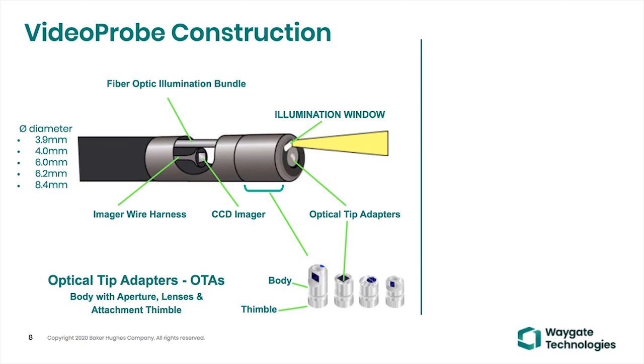And then the thimble is that bottom threaded part. Okay, and you're saying, okay, Thompson, why are you talking to me about those? People sometimes forget to clean them every time they put them on and take them off of a scope, and that's one of the high wear areas. I'll show you a picture of these thimbles in a magnified scene in a moment, but the thing I want you to take away from that, it's a significant investment, and if you take care of them, they have lasted 20 years or more.